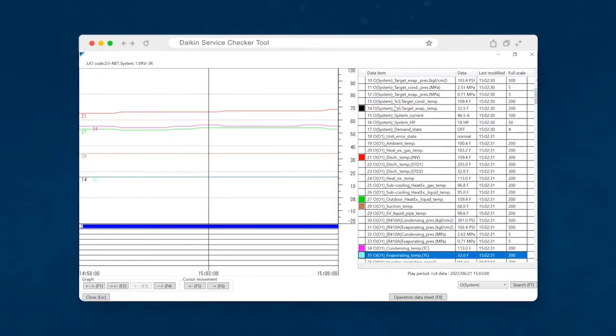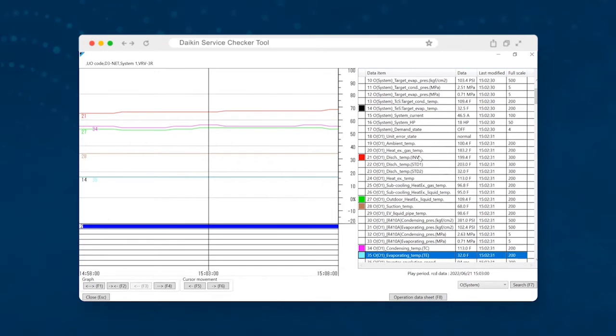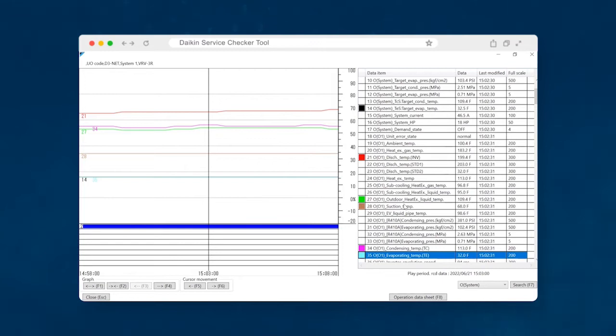So you have a ton of data here. It's all important, but some of it is more important. Some of the pieces are more important than the others when trying to make a confirmation of adequate charge or lack of charge. So one thing that you'll notice is these are basically the same types of points that you would look at if you were judging superheat or sub cooling on a conventional system.